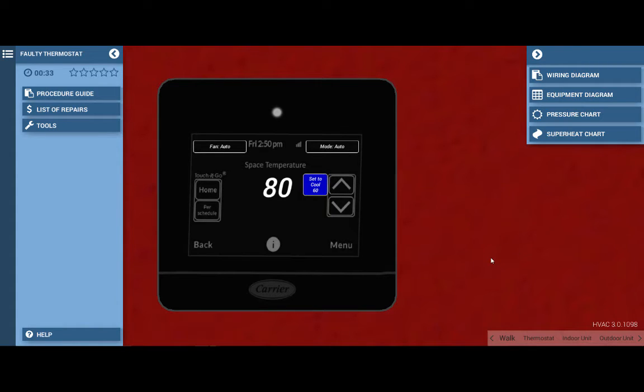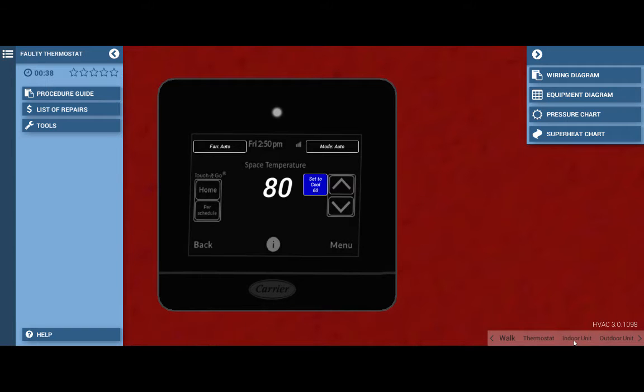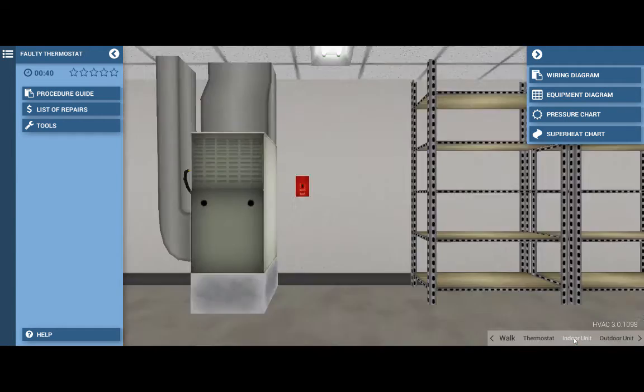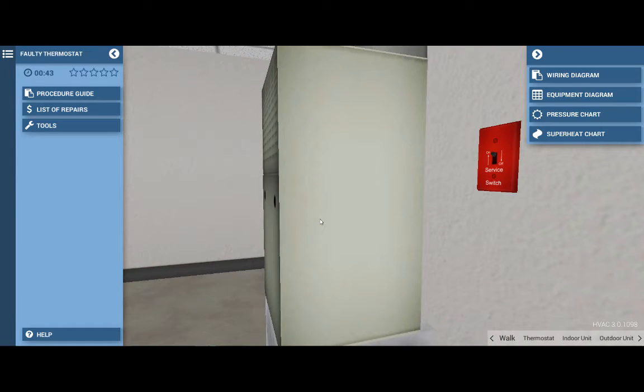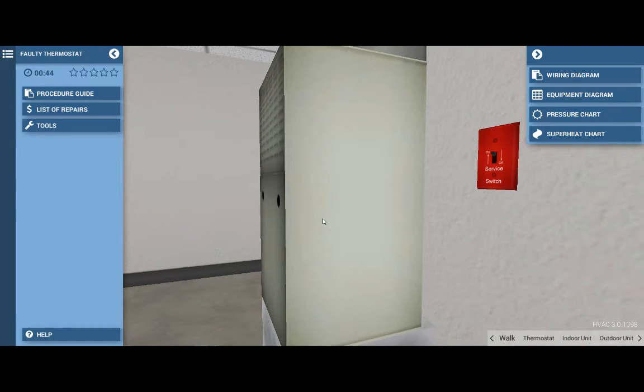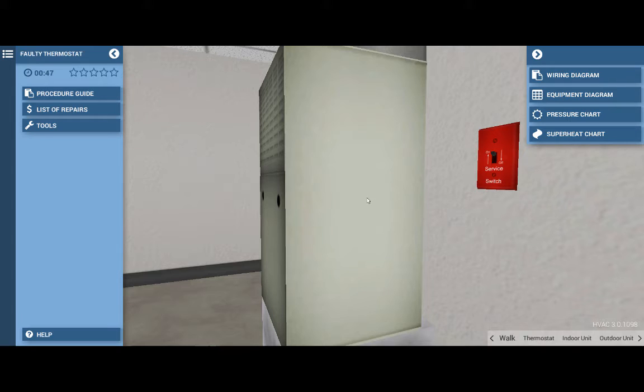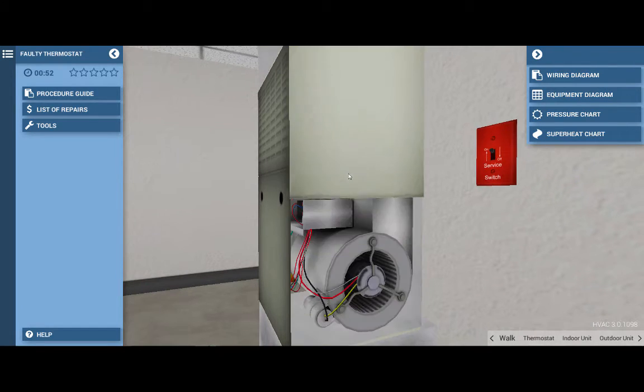Next, we want to go to the various electrical loads and see which of them are running. So we're going to start at the indoor unit. We're going to click on this indoor unit icon. And we don't hear any sound coming from the blower. You could also verify if there's air coming out of the registers.